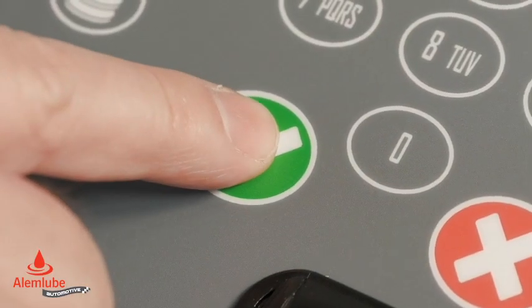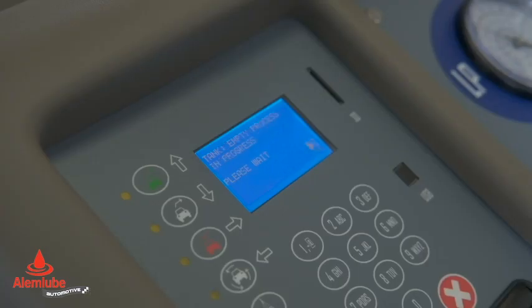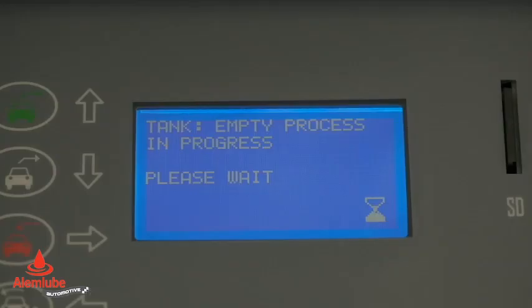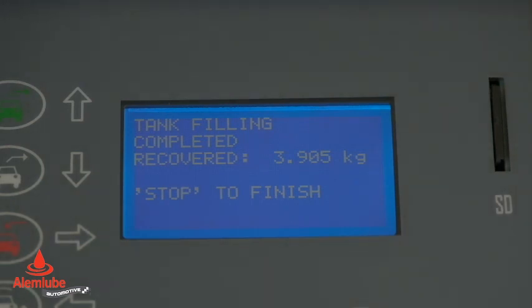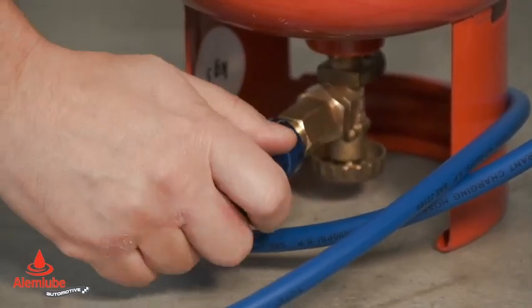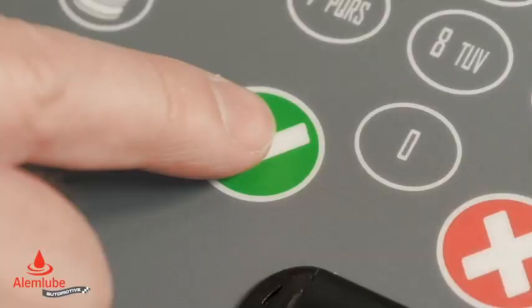Press enter to continue. At the first installation, the function will start with 10 minutes of vacuum in the internal cylinder to eliminate residual air. Then it will automatically start to recover the gas. When the filling function is finished, close the valve of the external cylinder and press enter to complete emptying the tubes.